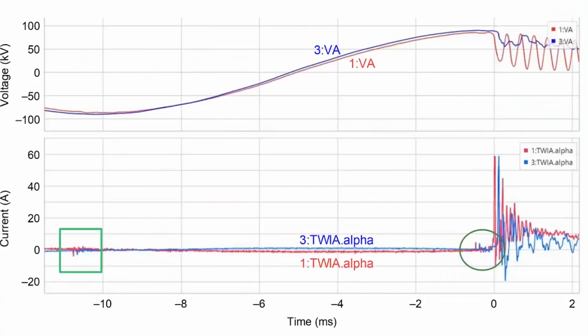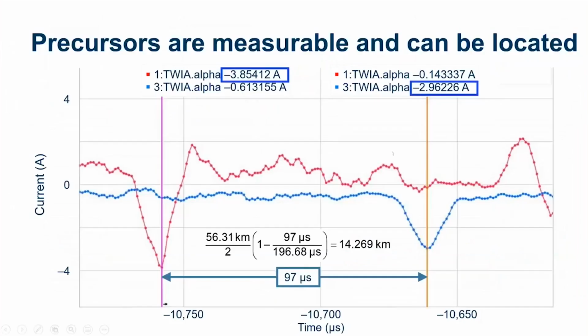So this slide shows these precursors that I was discussing. What's shown on this slide are these large traveling waves on the far right, starting at time equals 0. This was an actual fault that occurred. But before the fault occurred, we saw some traveling wave events happen. If we zoom into these traveling waves, we can see the red trace, which is from one terminal of the line, and the blue trace is from the other terminal of the line.